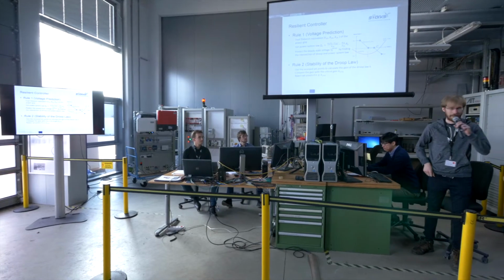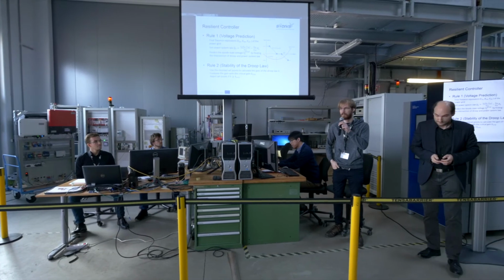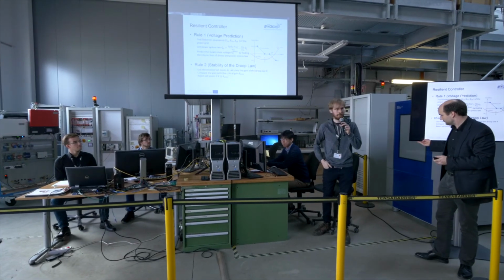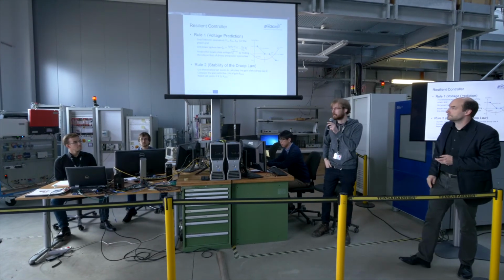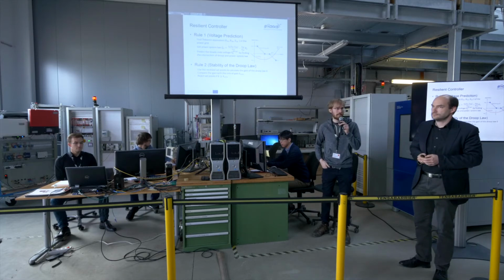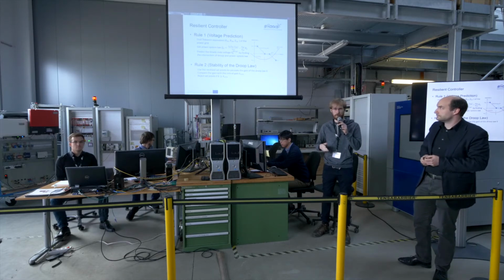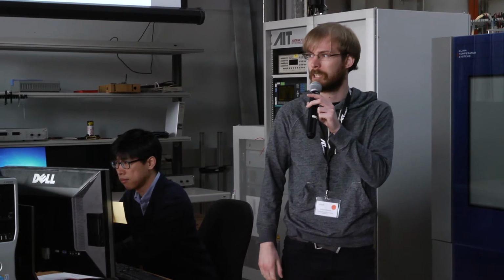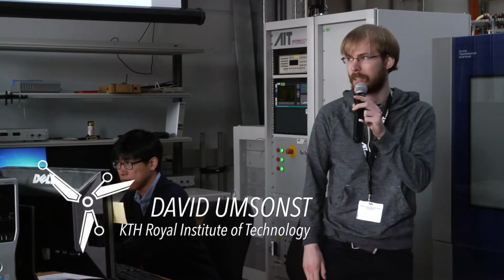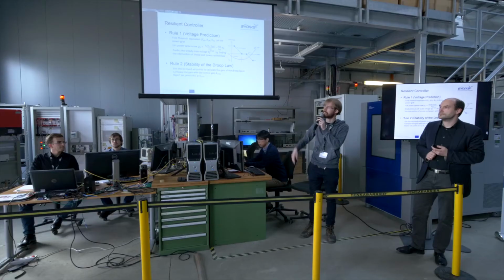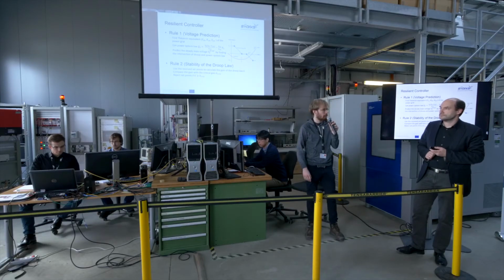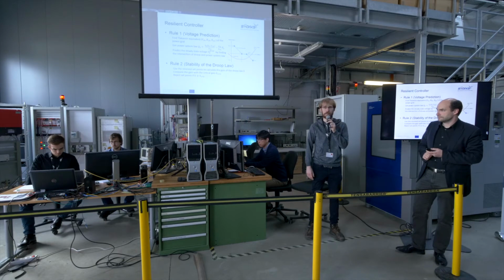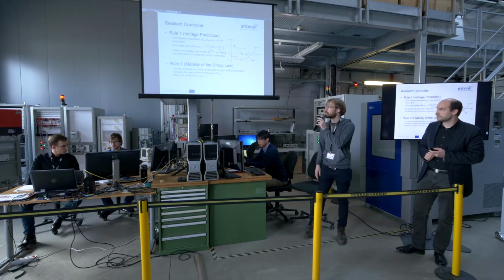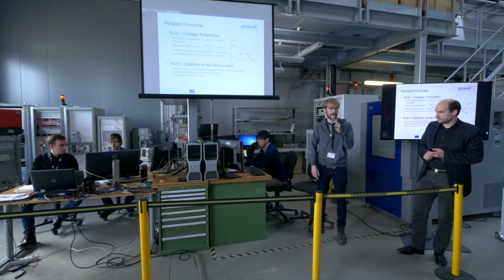Sure. As already mentioned in the talk by Henrik Sandberg, we have implemented two rules. One is for voltage prediction. This basically approximates the whole grid from the perspective of the PV as a Thevenin equivalent, just an impedance and a voltage source. With that we get the power system law, as you can see in the slides, and then we look for the intersection between the Droop law and the power system law. That intersection point gives us the new steady state voltage the system should converge to with this Droop law.